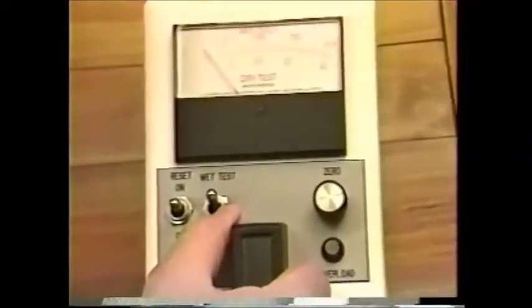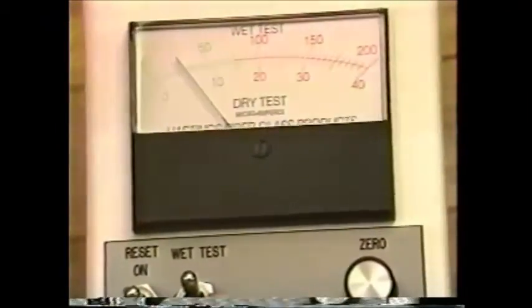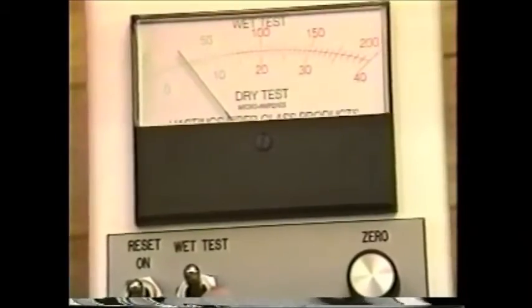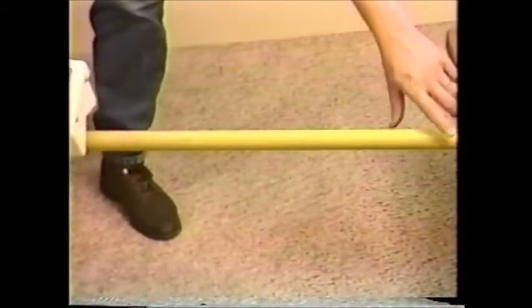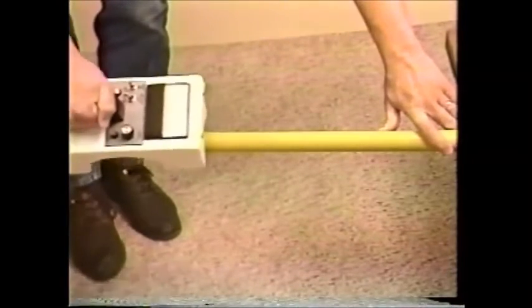The dry test is not required by OSHA. It can be used as a tool in determining the integrity of the fiberglass prior to wetting the surface. It is possible for a tool to be cracked or deeply scratched and hold moisture for long periods of time. Internal contaminations on hollow tools can also hold moisture that can be detected with the dry scale. Our recommended acceptance value is 15 microamps.